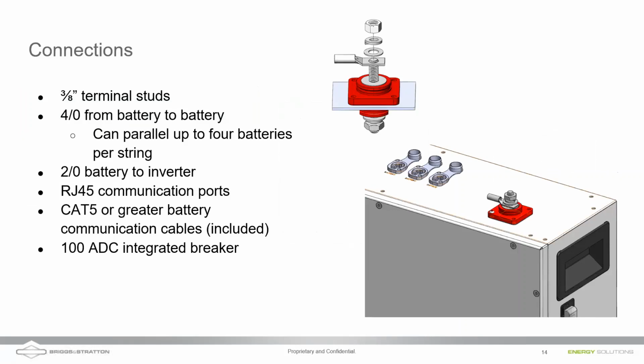Now, I do want to talk about the connections we're going to be making here. So it's a 3/8 inch terminal stud. Previously, we were requiring each individual battery to be wired to a common combiner. So each battery would have their own set of cables and their own home run, and there'd be no daisy chaining allowed. However, in this configuration, with this new battery that's outdoor rated, we really want to reduce the number of additional components that you need to purchase and source and set on the wall. We want it to be a very clean looking installation with minimal extra components for you to source. So what we're doing here is we're allowing daisy chaining from battery to battery. And we'll talk about what that looks like if you're not familiar with the daisy chaining method.